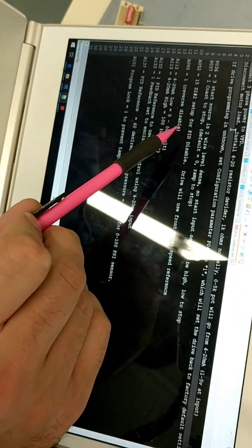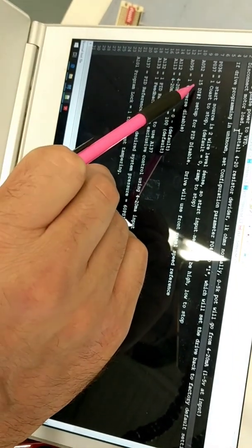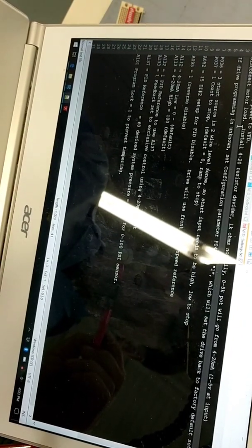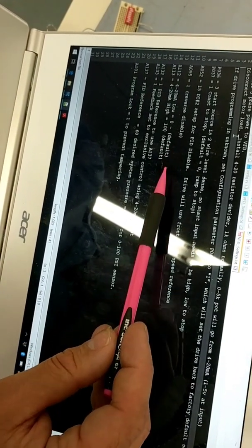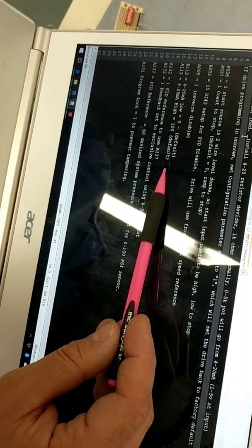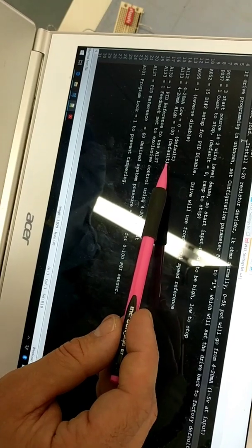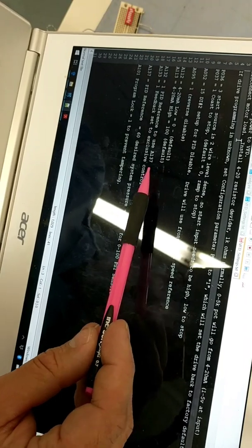Next, which is kind of unnecessary for the application, but I like it, A052 is for discrete input number 2. When that is set with a value of 15, it's not going to use the PID loop. That's PID disable, and the drive will just use the front panel speed reference, the potentiometer on the front panel. For a water pump, we want to disable the reverse. These two are not necessary. You would invert these if your sensor was wired differently.